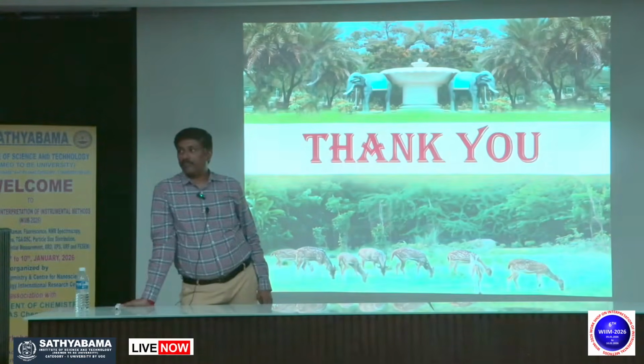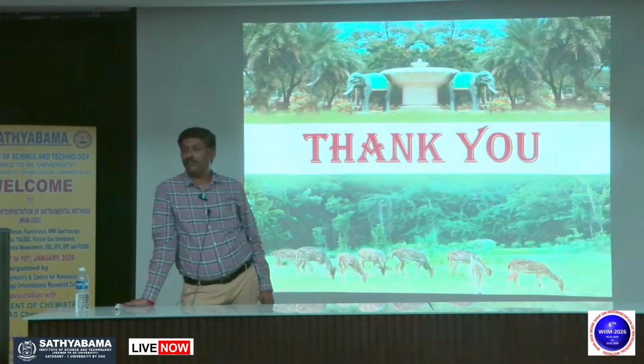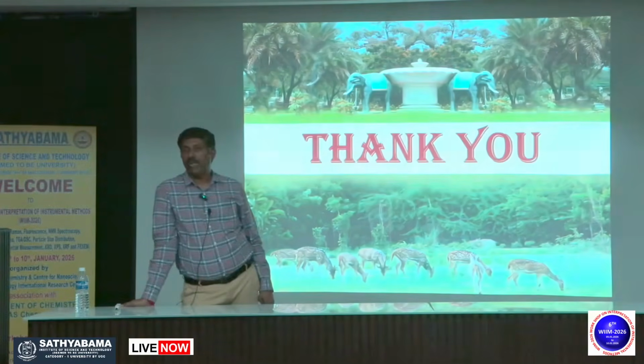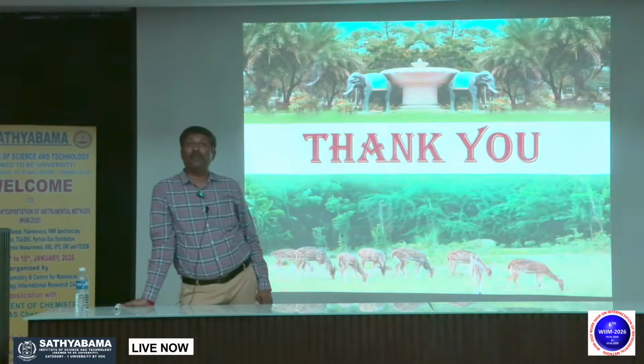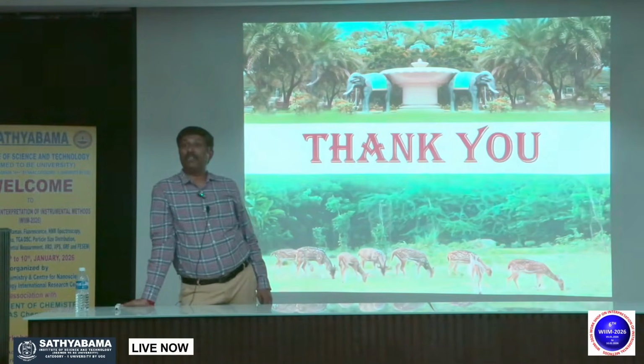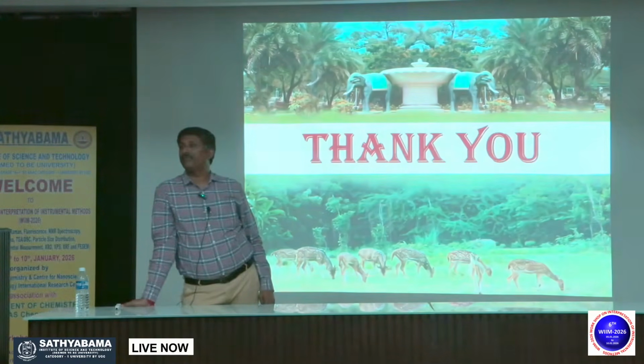In TGA, we will be hanging the sample. Is there any gravitational effect? While hanging, maintaining temperature and these conditions, mostly we will be using horizontal. It's the best, whether horizontal or vertical, I don't know. It depends on how calibration has been done and whether you have a reference or not. So this effect can be nullified through calibration and through a reference.